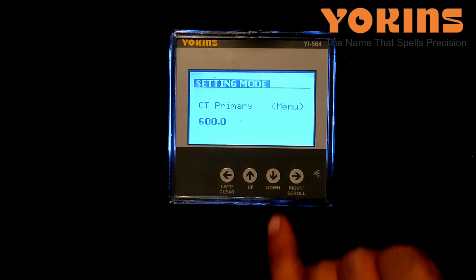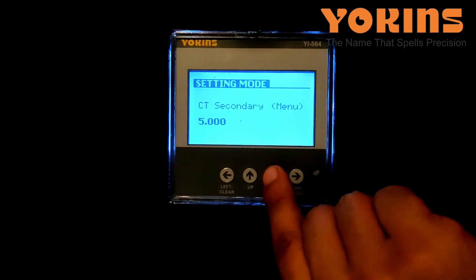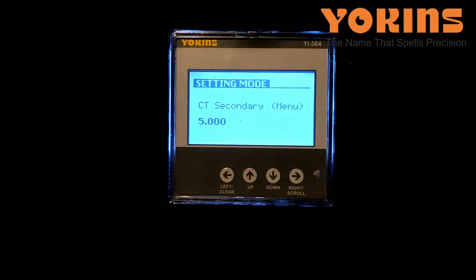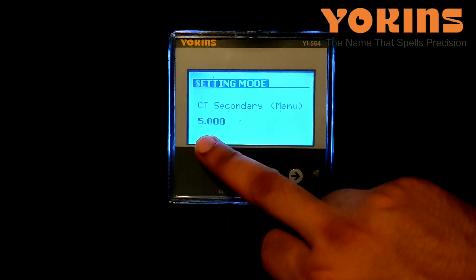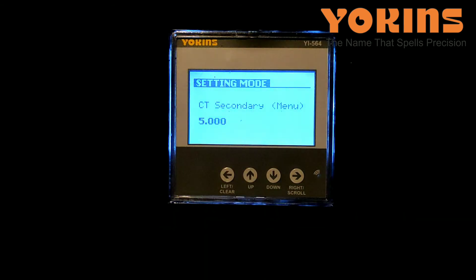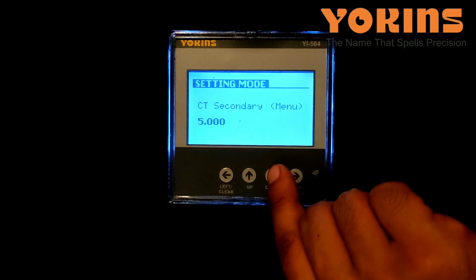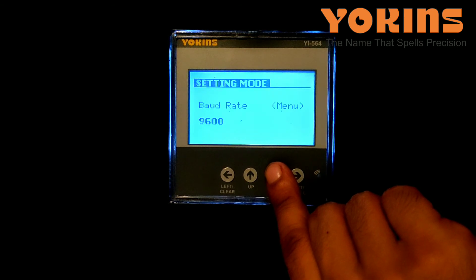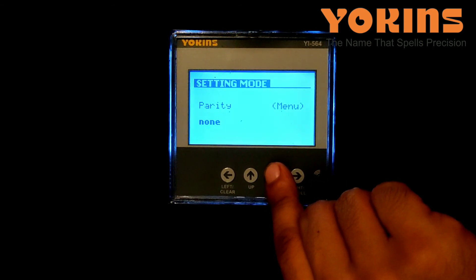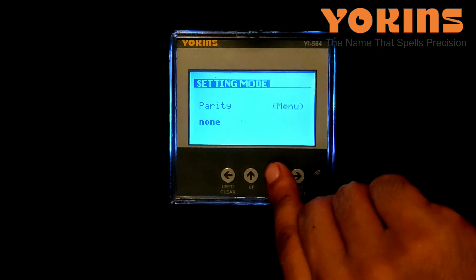Now 600 is selected. We'll press the down button — CT secondary is shown. We need not change CT secondary since our CT ratio is 600/5A. However, if your CT ratio were 100/1A, you would need to change the secondary from 5 to 1. Then pressing down button shows baud rate — this is for RS-485, and we can select from different baud rates. Next is parity, also for RS-485.